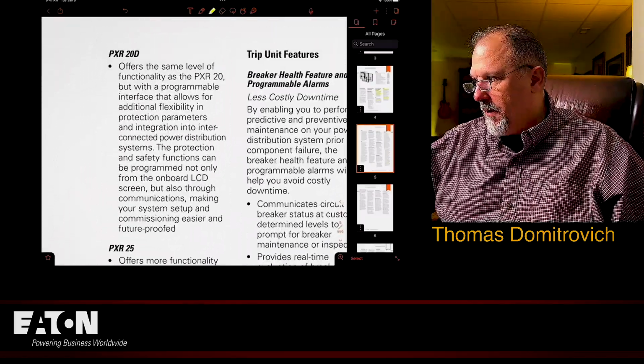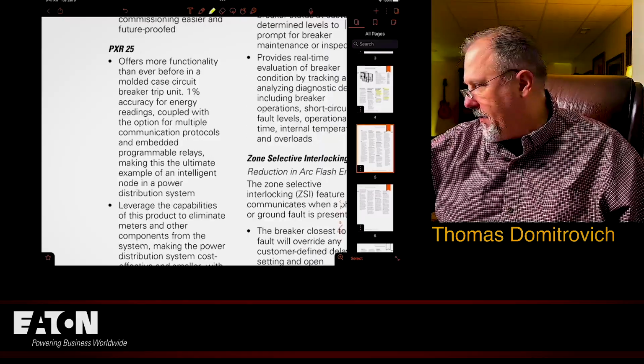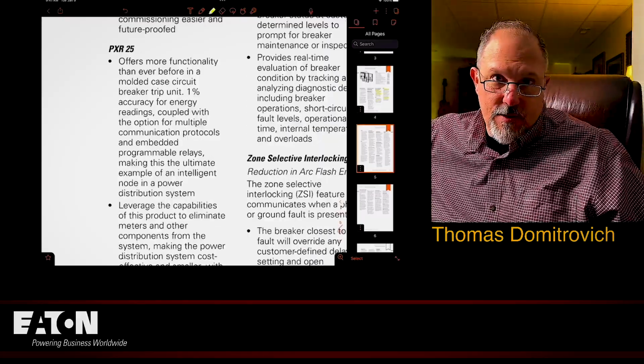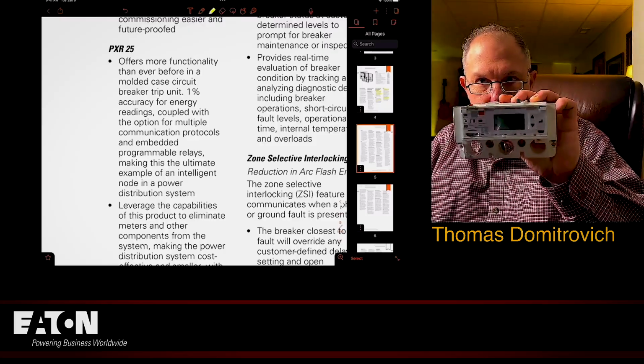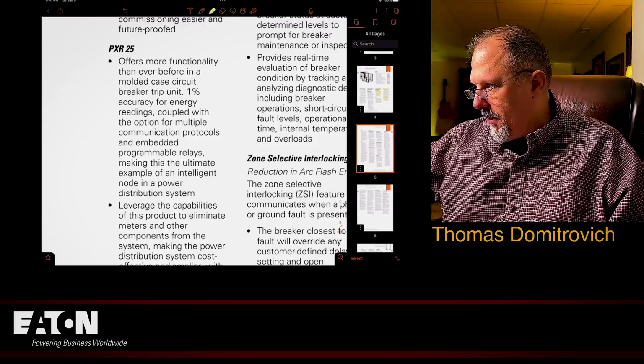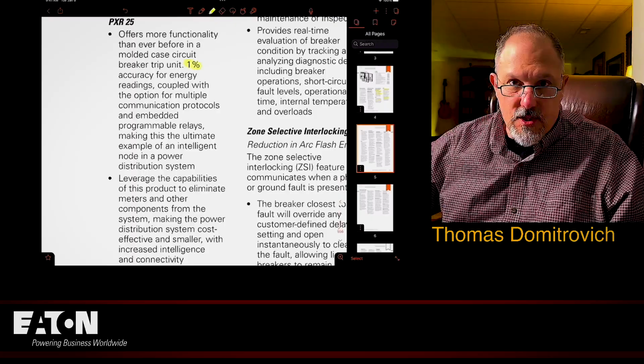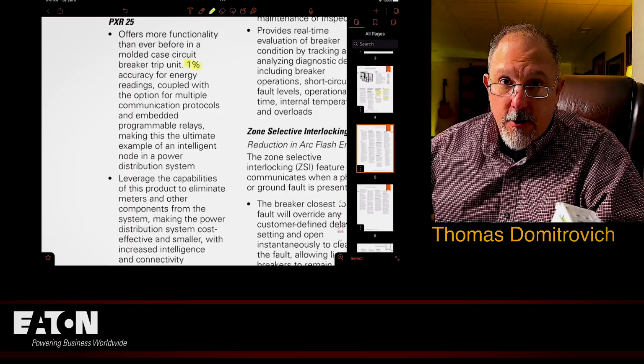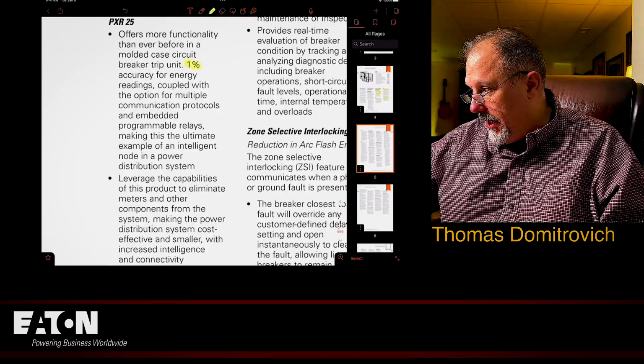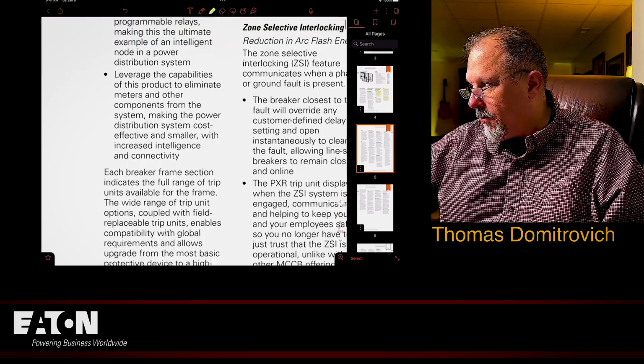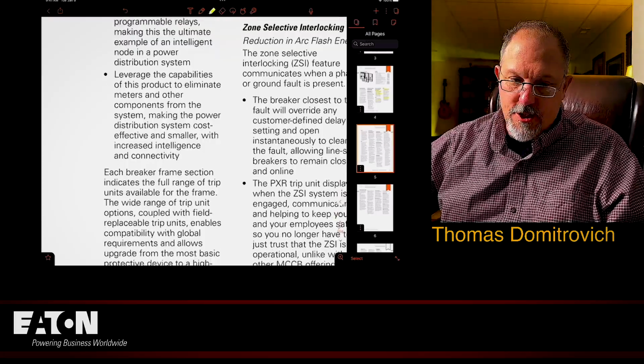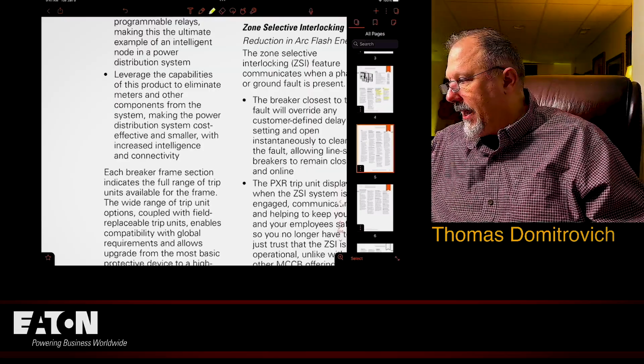You have a PXR20D, fine. Then you have the PXR25, and the PXR25 is this one. And it has additional capabilities. It has a 1% accuracy because it'll do energy monitoring for you as well. It has programmable relays, and it has an arc flash reduction maintenance switch on it, capabilities as well.